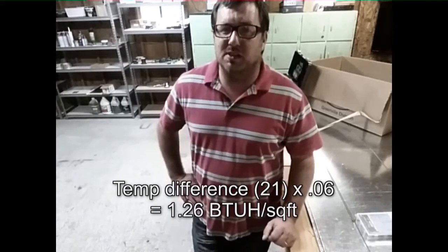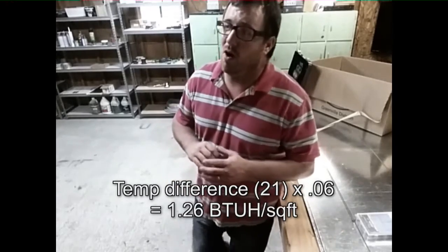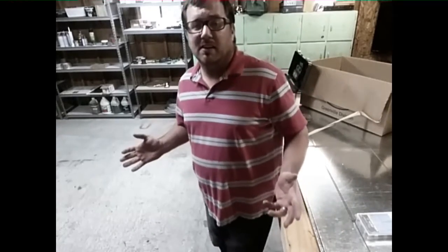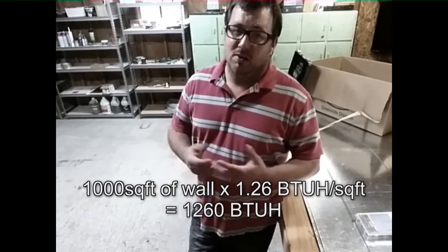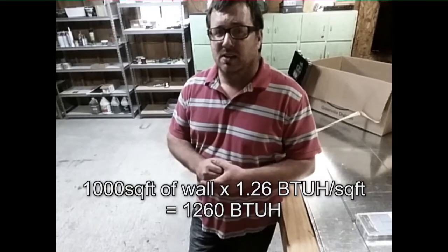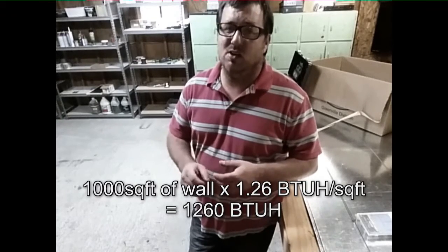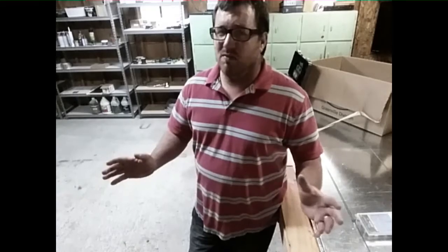So 1.26, and let's say our wall is 1,000 square feet. We have 1,000 square feet of wall. So 1.26 times 1,000 is 1,260. So 1,260 BTUs per hour will pass through that wall based on what we designed. And that's just one example of what we're going to do. But you can sort of see where we're going. We can do that in different aspects, in the attics, all over the house, based on what design we want.